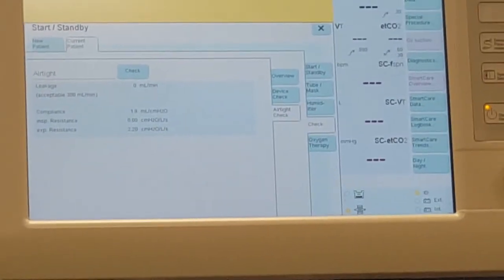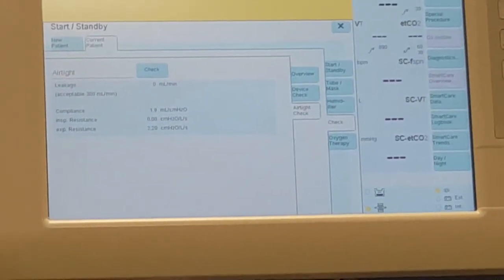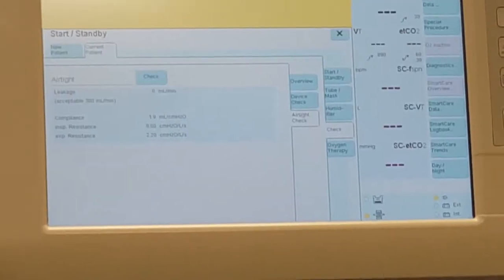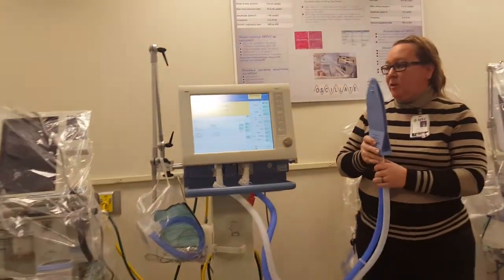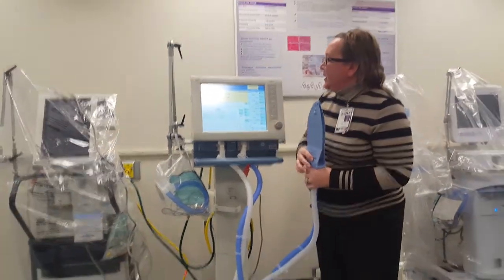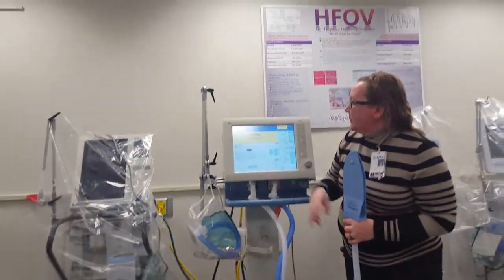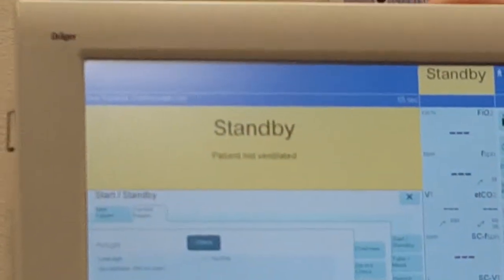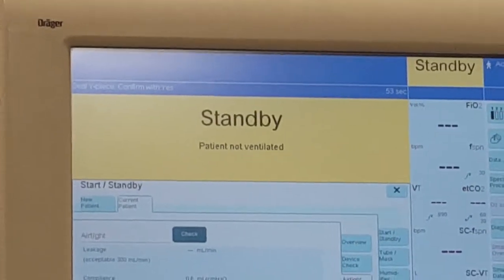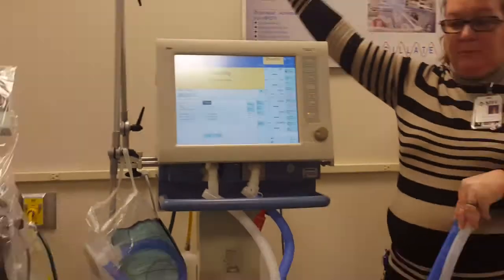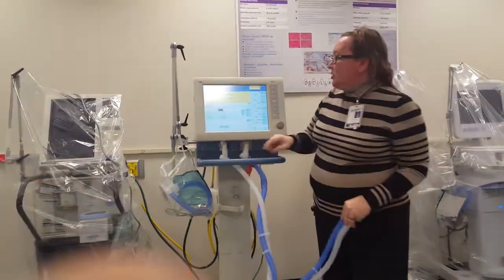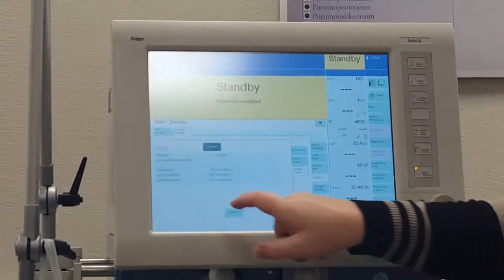Now we're going to go to the airtight check. And now this is going to check for the patency and any leaks in our circuit. This one is a little weird because you can't really tell for sure when it's done unless you're paying attention, unless you know what you're looking for. So I'm going to tell you what that is. So you're going to hit the word check. Seal Y piece, confirm with yes. Seal Y piece, remember, is always to seal it. This is not sealed. This is a patient. This is sealed. So seal Y piece, confirm with yes.